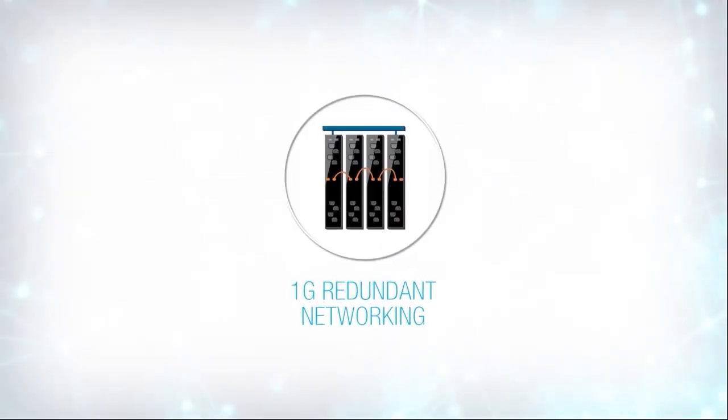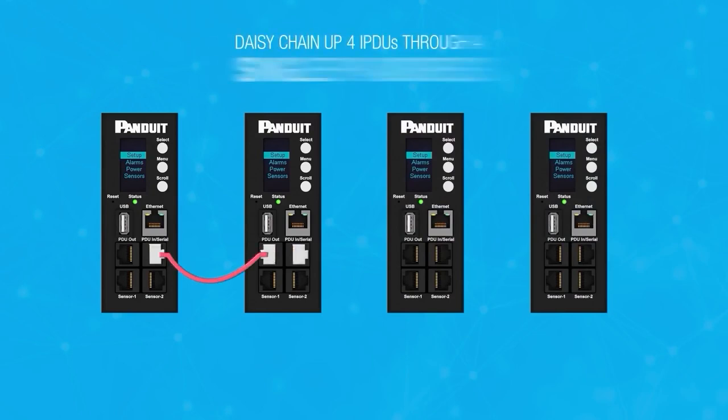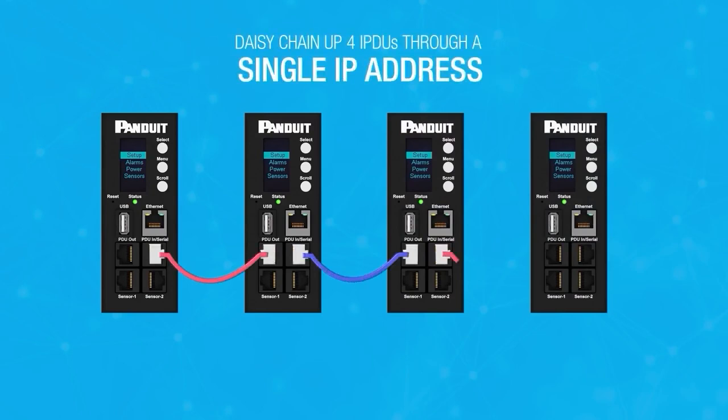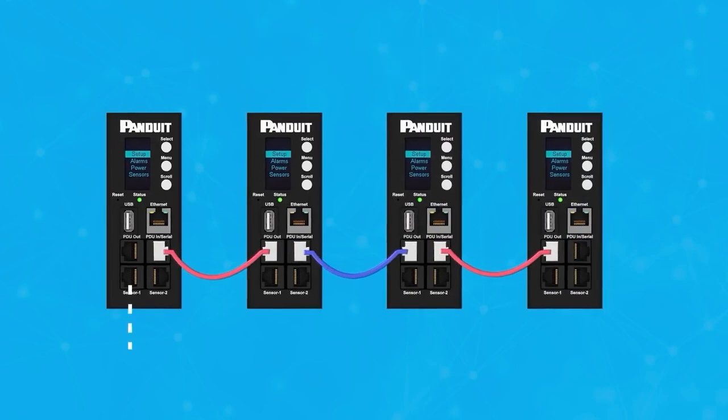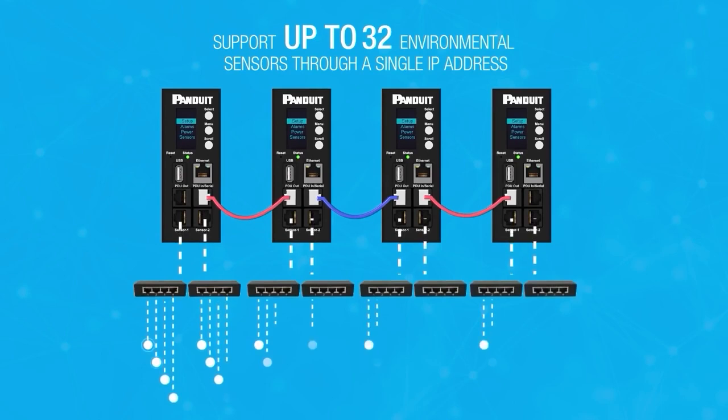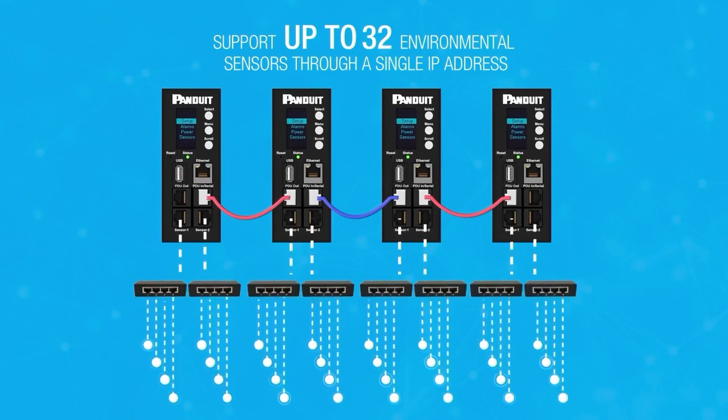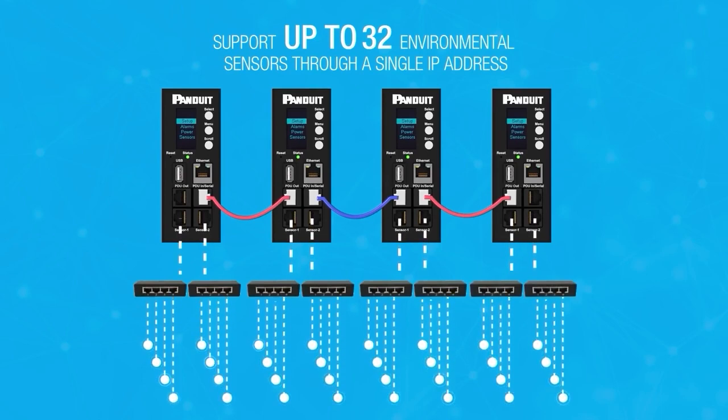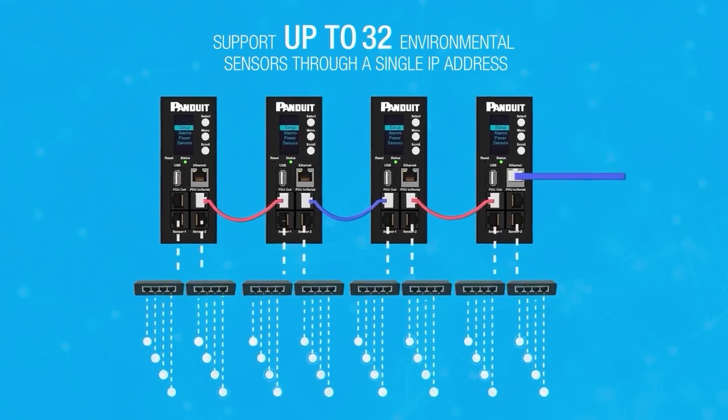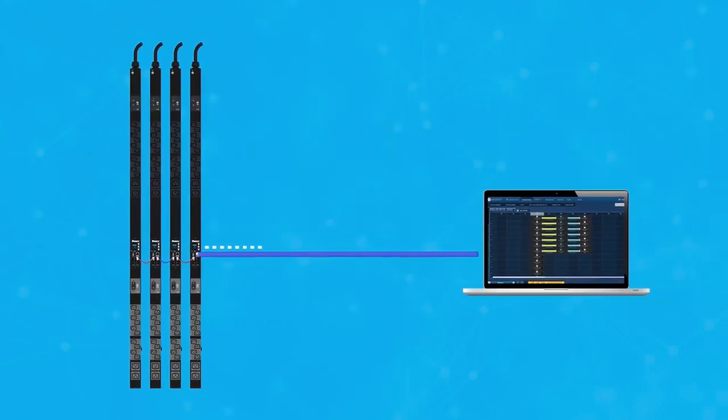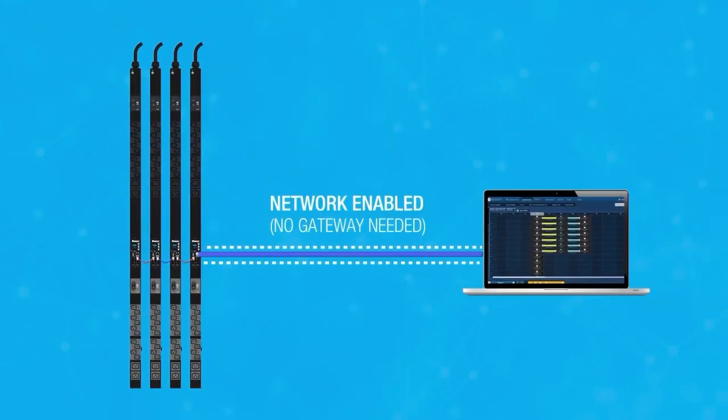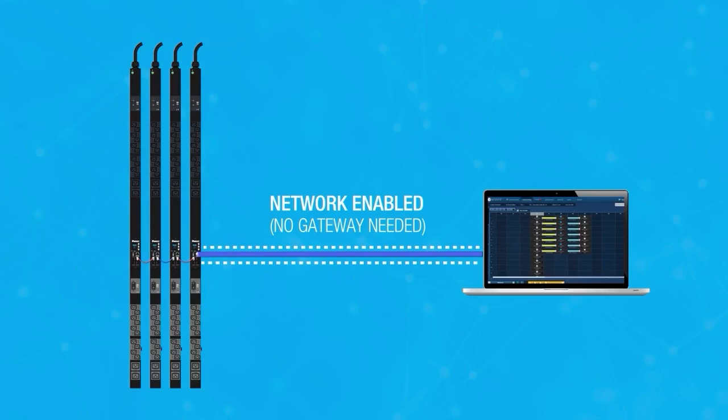With the G5 PDU's ability to daisy chain, it's possible to control four IPDUs and up to 32 environmental sensors, all from a single IP address. In addition, the ethernet port and built-in intelligence allows direct two-way network communication without the need for a gateway.